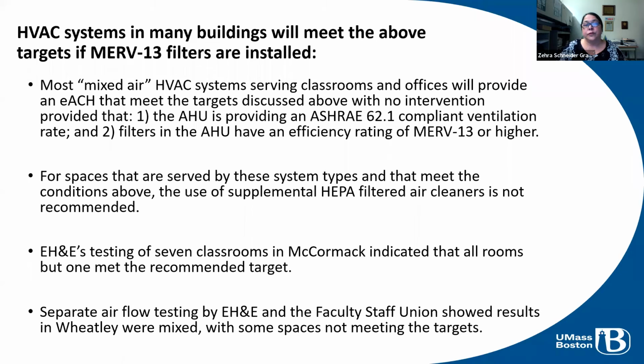No ventilation interventions are used to address offices where there's a single occupant. HVAC systems in many buildings will meet the above air targets if MERV 13 filters are installed. So most mixed air HVAC systems serving classrooms and offices do meet effective air change rates with no intervention, as long as the air handling unit is working and providing ASHRAE 62.1 compliant ventilation, and that the filters have been upgraded to the MERV 13. For spaces that meet those targets, we don't use supplemental air cleaners, and they're not recommended by the governing bodies.